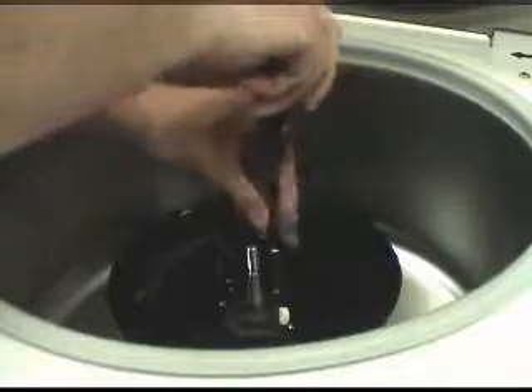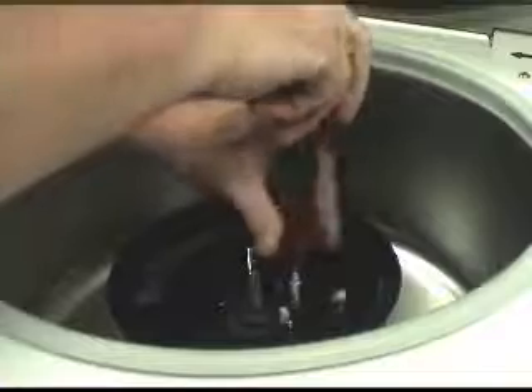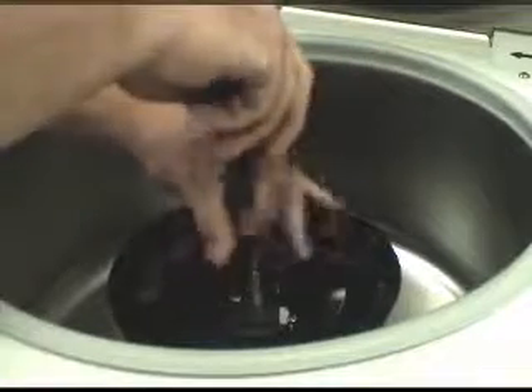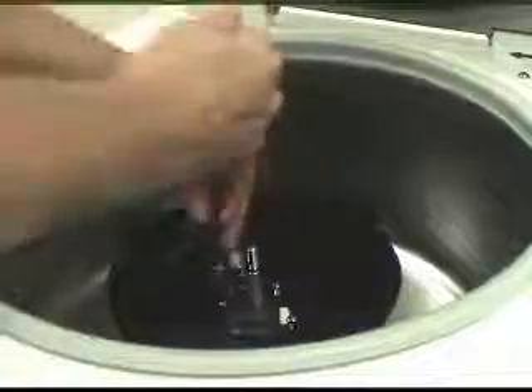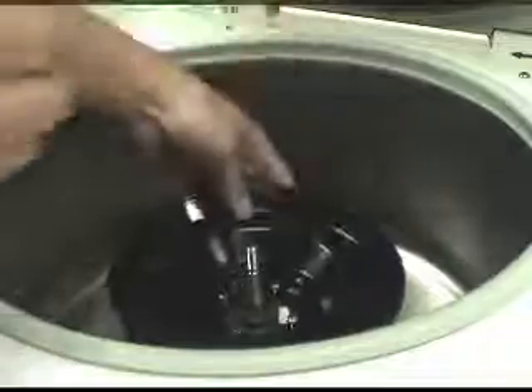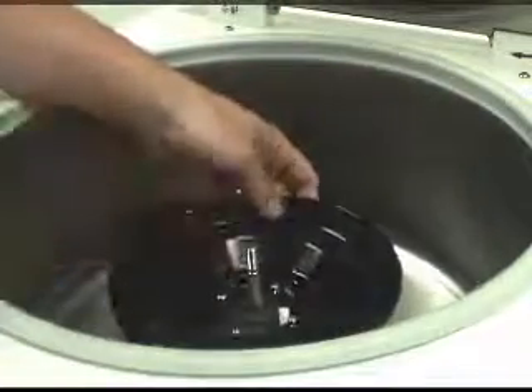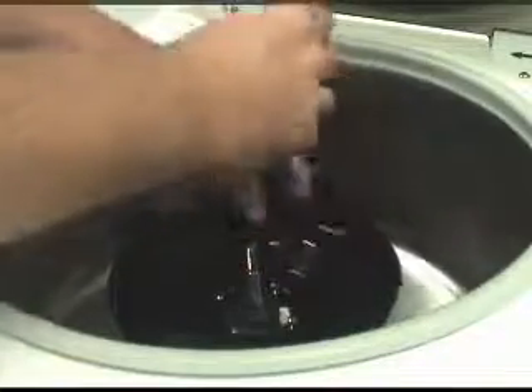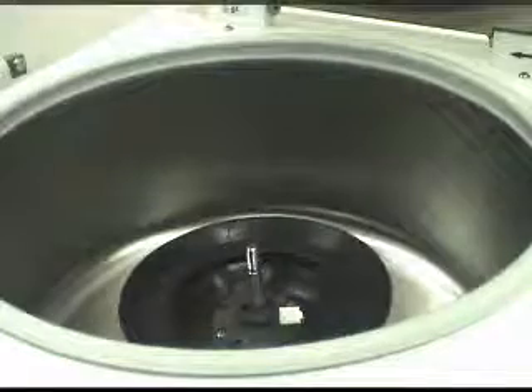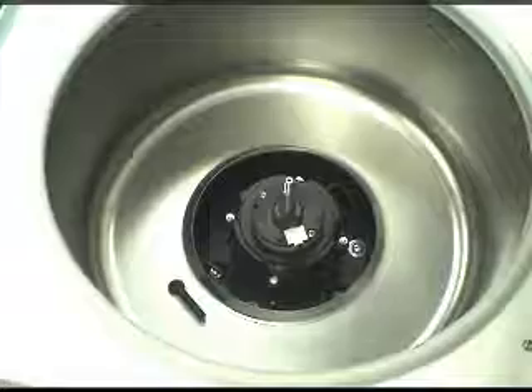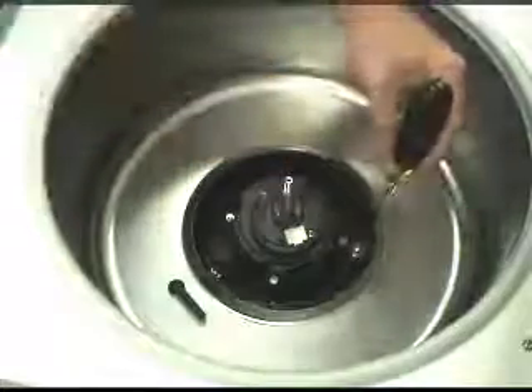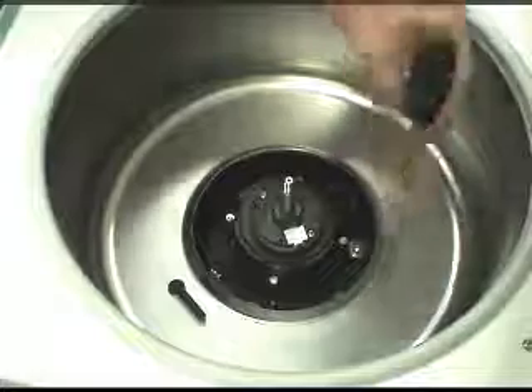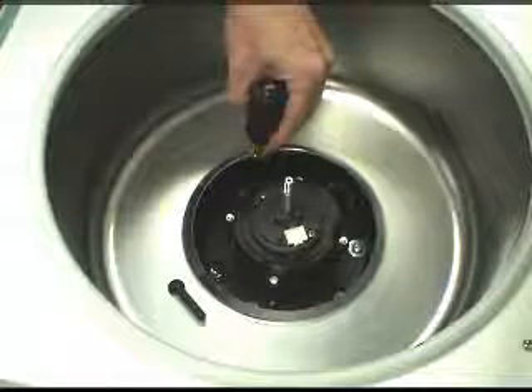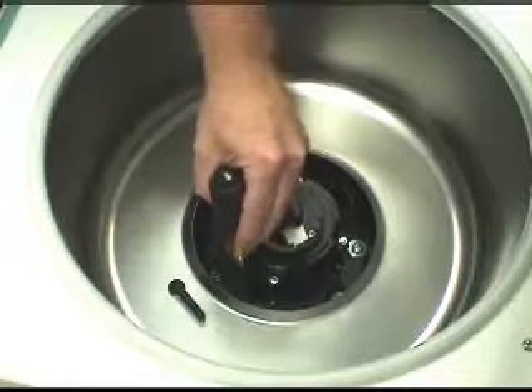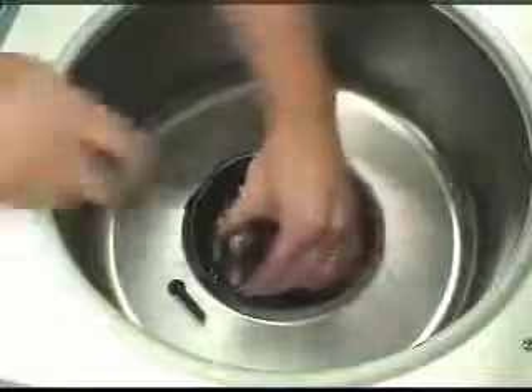Remove the 4 screws that hold the motor cover upside down on top of the motor. Remove the rubber gasket as well. Remove the 3 transport bolts located here, here, and here. They're large Phillips head screws.